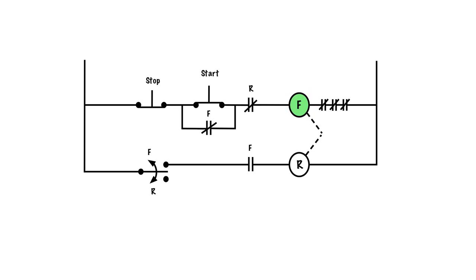This coil stays energized or becomes energized, pulls in the F contacts down here which are physically attached. This coil controls these contacts, and when I let go of this start button it will hold in and keep running.